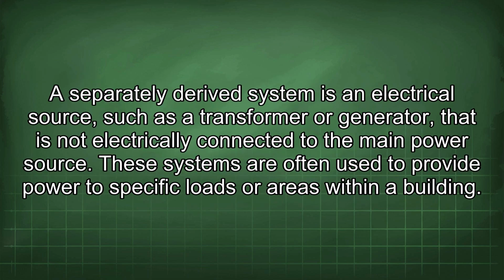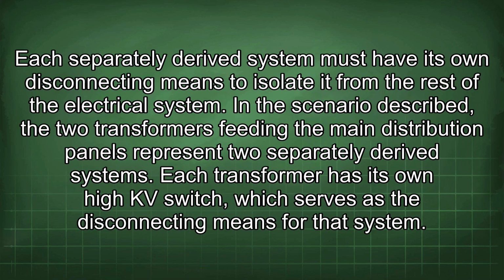A separately derived system is an electrical source, such as a transformer or generator, that is not electrically connected to the main power source. These systems are often used to provide power to specific loads or areas within a building. Each separately derived system must have its own disconnecting means to isolate it from the rest of the electrical system. In the scenario described, the two transformers feeding the main distribution panels represent two separately derived systems. Each transformer has its own high kV switch, which serves as the disconnecting means for that system.